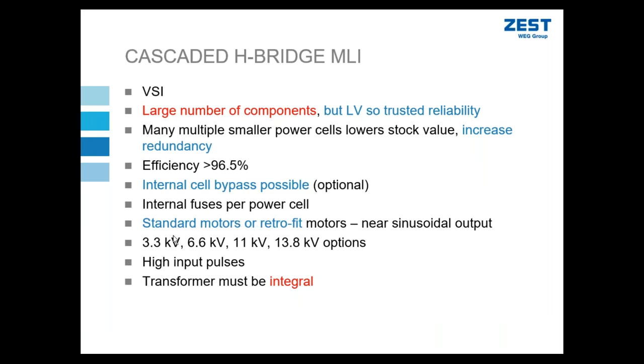The one advantage here is that I can use this on standard machines or retrofit machines. In most cases, bear in mind, we still have a pulse width modulated output, so the motor does need to be taken into consideration. But I can increase the number of levels of my output voltage on this topology, which is helpful and beneficial to my motor.